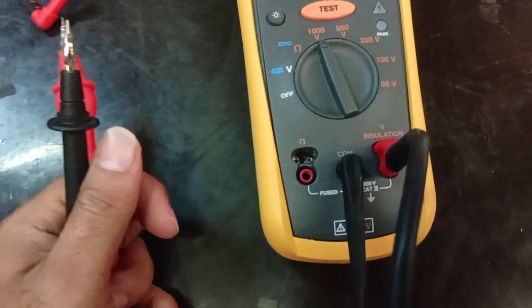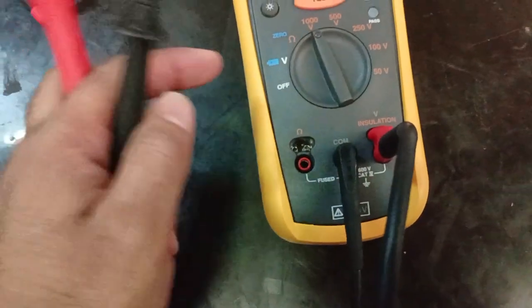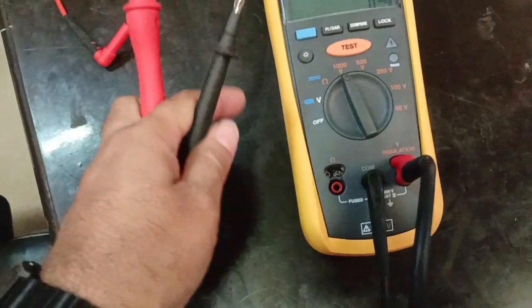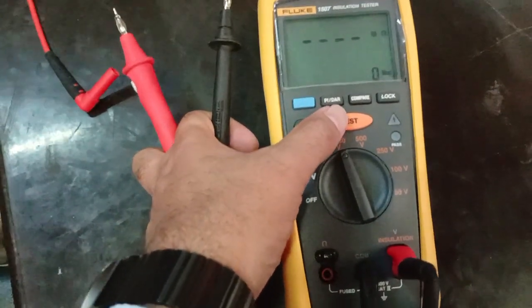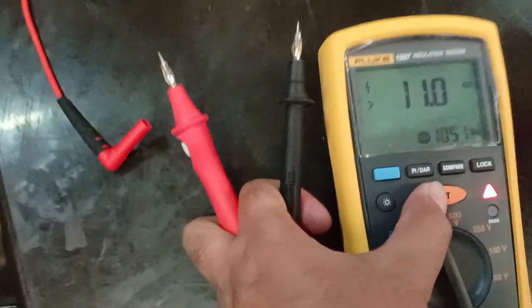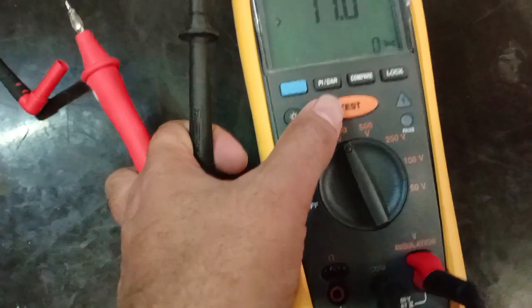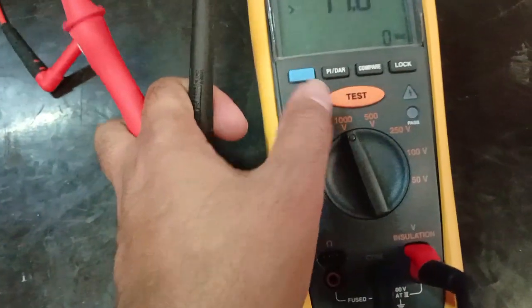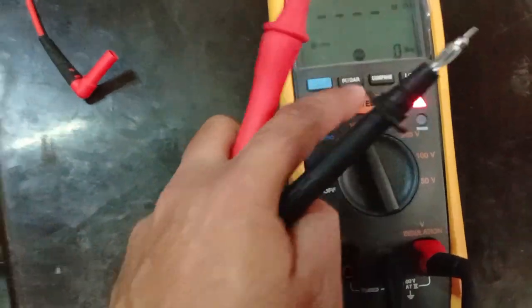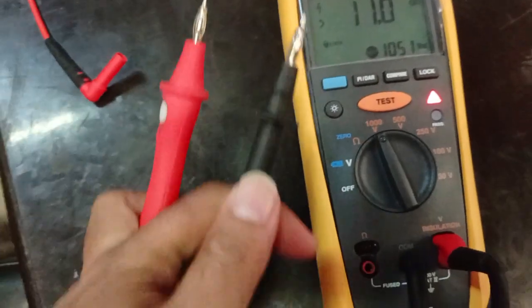Now we will do the insulation megger test. We put this knob to the 1000V position. Once I press test, there will be voltage going inside this terminal — it means there is power at this terminal. Once I release the button, the power cuts off. If you lock first and then press test, the voltage will continuously inject through this terminal to the cable.